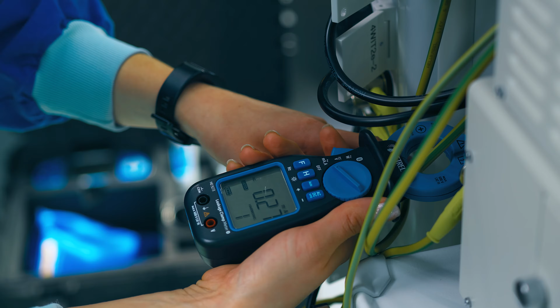A thorough safety inspection, in case an insulation monitoring device sounds an alarm, is therefore a must. The MD9273 clamp meter is a useful ally in this and can be used to quickly check devices with exposed protective earth cables and identify the faulty device.